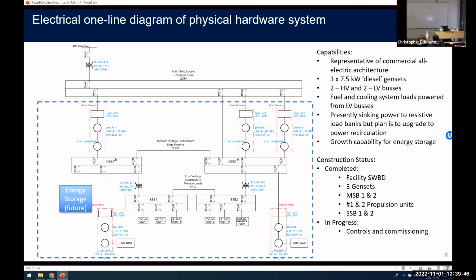The three generators themselves feed two main buses. These two main buses are three-phase and at 208 volts as well. The three-phase buses feed two propulsion systems, which are both three-phase. Our secondary systems are fed off the secondary switchboards, which are isolated with the delta Y transformer below. So we take the three-phase power of the main switchboard and run it through a delta Y transformer. This way, for the secondary bus running the cooling pumps and fuel pumps, the loads are balanced on the generators themselves.